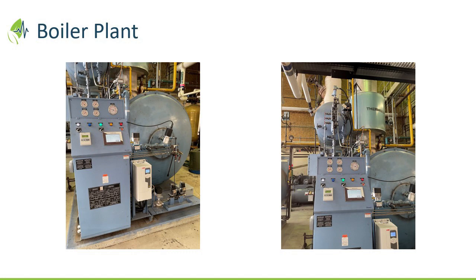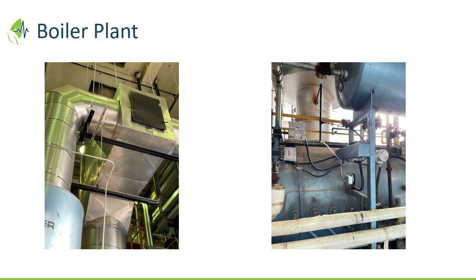I have one more question. In terms of the stack, aren't those built for dispersion needs? When you change the flows out of the stack, does that make it disperse less? I know we do certain things for safety, it costs us energy. So is there no issue with the dispersion from the stack if you start changing these things? In theory, if you're very tight with your combustion and your draft control, then yes, you won't have the velocities coming out of the top of the stack. However, we're combusting exceptionally clean, so that's what we're managing at the boiler. And besides, those stacks are designed at such a height that they're sending it well away. My second question relates to technologies like adding additives to the fluid to improve resistance. Is any of that viable?